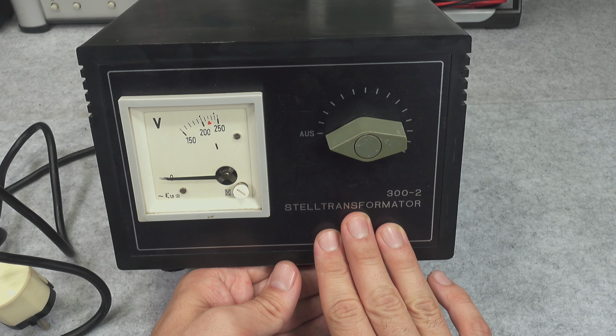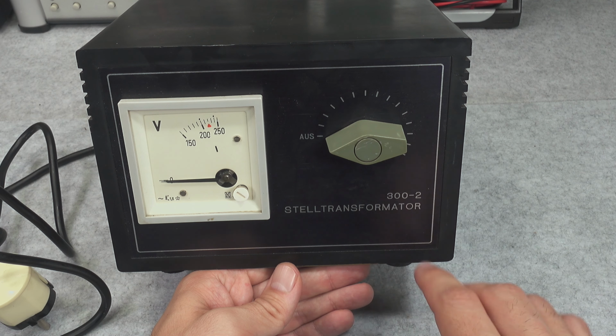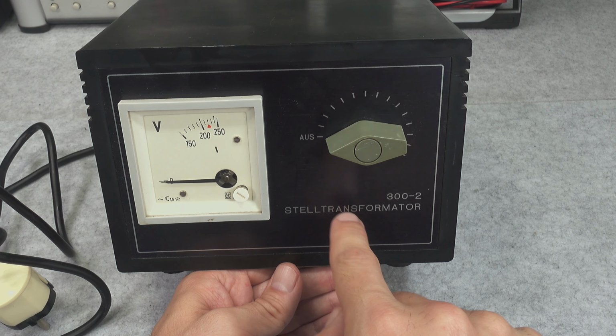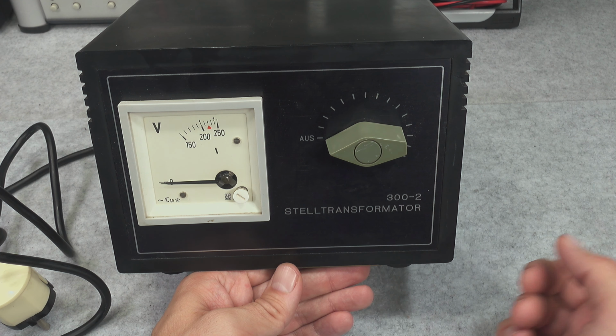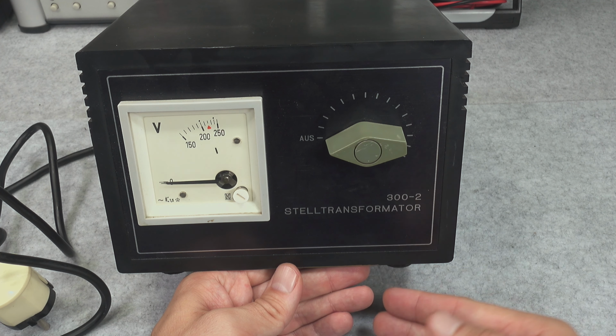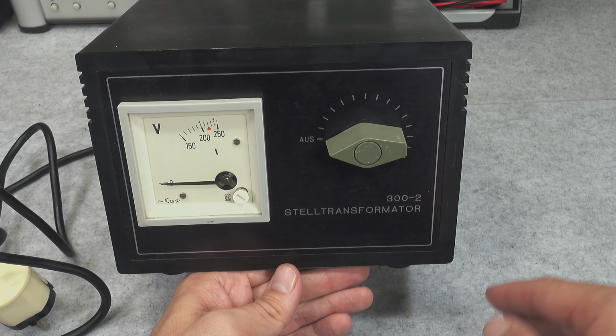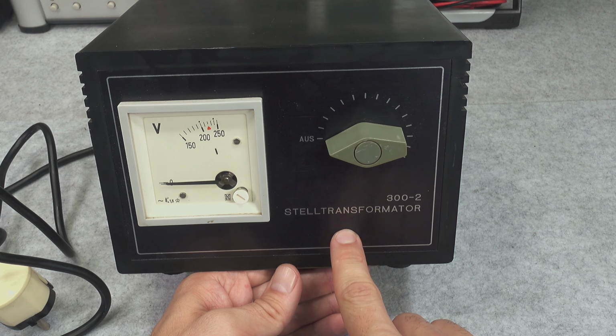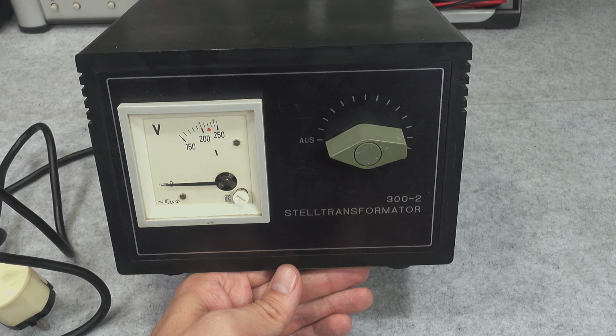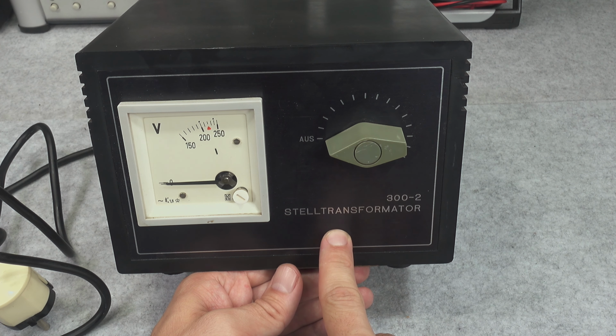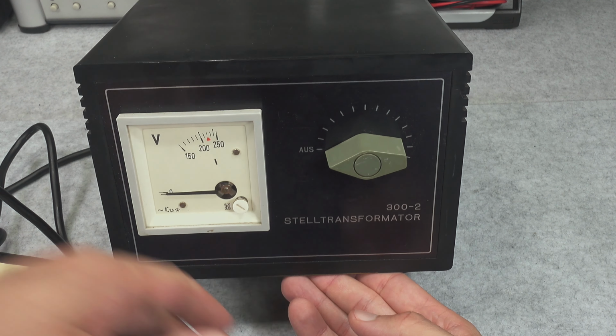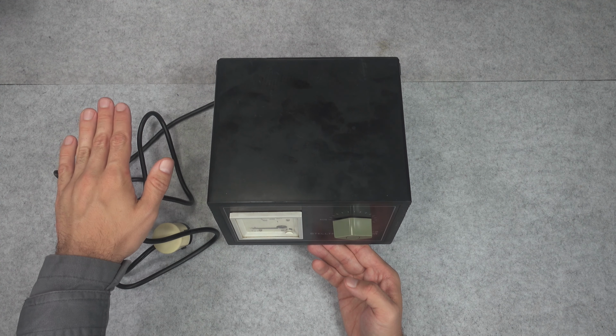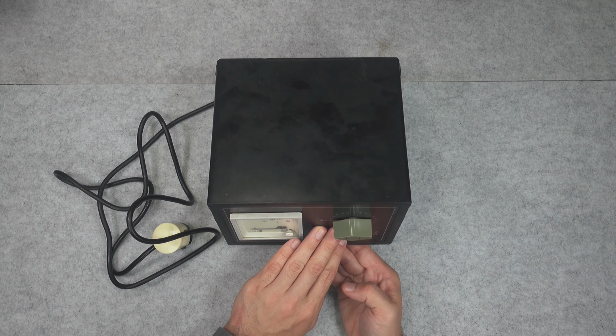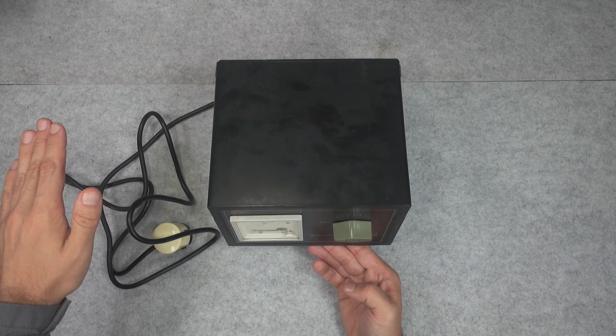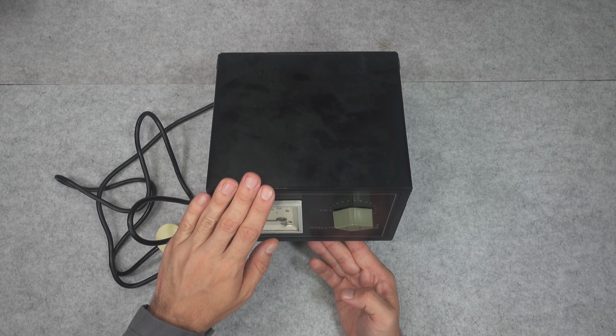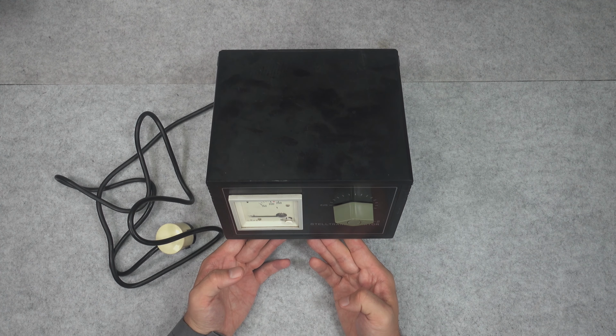What is critical for you to know is that autotransformers by design do not provide galvanic separation, so this is not a device that you would like to be using while working with AC power systems if you would like to probe it with your oscilloscope that is ground referenced. This will not provide galvanic separation. There are instruments that combine two devices at once, with a built-in isolation transformer plus an autotransformer for regulating voltage, but they are usually twice the size of that box for the same power, and this is a dead giveaway.